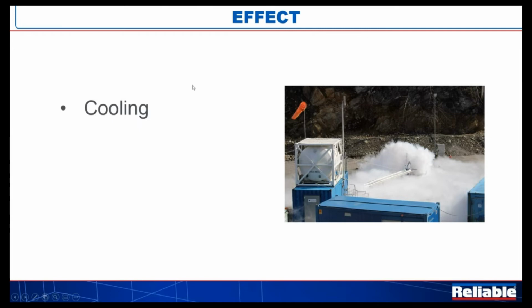Well, the finer drops don't give us the fire plume penetration that we have with the high velocity. We're going to use these on lighter oils. Again, we'll see in a second, but lighter oils really don't emulsify, so it doesn't do us a lot of good to splatter the top of those oils. The mechanism just doesn't work properly when the oils are a lighter weight. So the primary effect of the medium velocity nozzle is cooling.